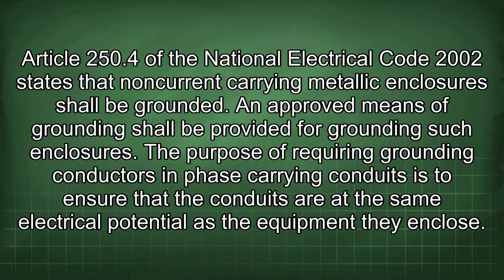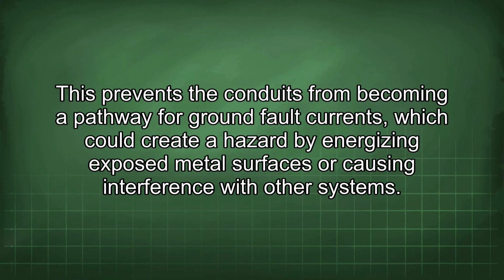Article 250.4 of the National Electrical Code 2002 states that non-current carrying metallic enclosures shall be grounded. An approved means of grounding shall be provided for grounding such enclosures. The purpose of requiring grounding conductors in phase carrying conduits is to ensure that the conduits are at the same electrical potential as the equipment they enclose. This prevents the conduits from becoming a pathway for ground fault currents, which could create a hazard by energizing exposed metal surfaces or causing interference with other systems.